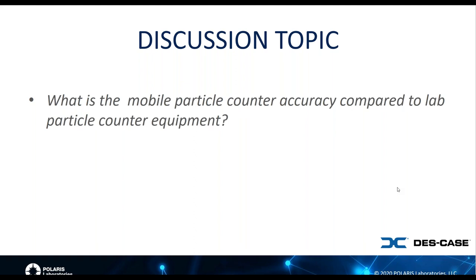But I agree with you, Julio, in what you said. You have to be really careful, because a lab instrument uses a method of light scatter, whereas most of the mobile particle counters on the market today use light blockage. When you use light blockage, if you have a very clean sample, there is no light blocked. So essentially the sensor is seeing almost 100% of the light, and that's a very high background. If you have a very small particle flowing through that sensor, the shadow is very small. You're starting to see a small change on a very high background.